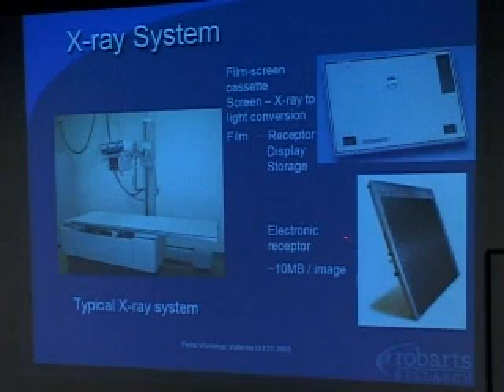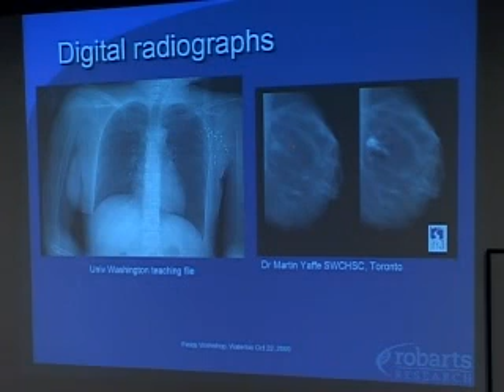This has recently been replaced by an electronic receptor, which has about the same form factor and can fit in the same sort of cassette holder on this X-ray system. But now we typically have 1, 2, or 3,000 by 3,000 detectors that can record the image. Digital radiographs now give us extraordinarily high-resolution images and high dynamic range, and as Dr. Babin pointed out yesterday, there are tremendous possibilities for processing these images to bring out subtle details that cannot be captured on film. An example from my colleague Martin Yaffe in Toronto, with this breast image, you can see this region, which has been enhanced by an image enhancement algorithm to really bring out the characteristics of this suspected tumor.